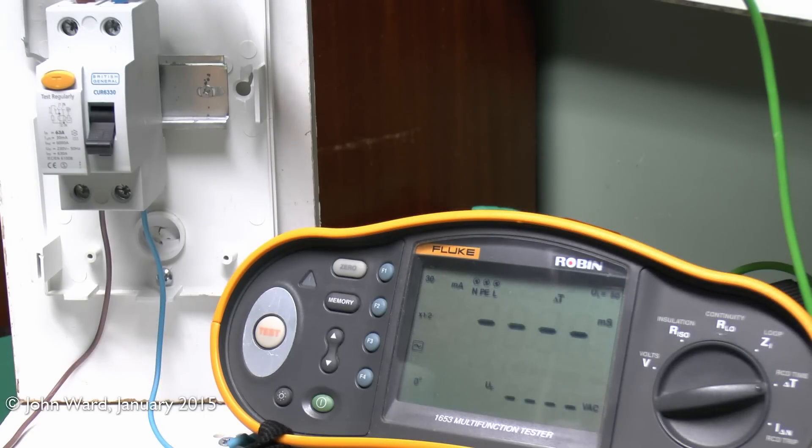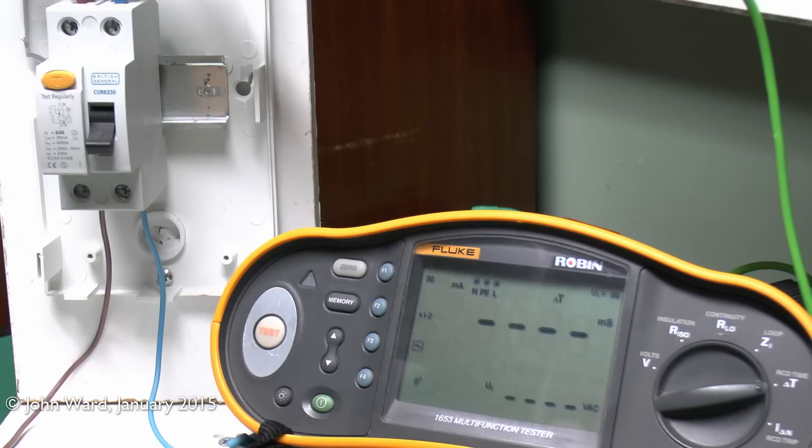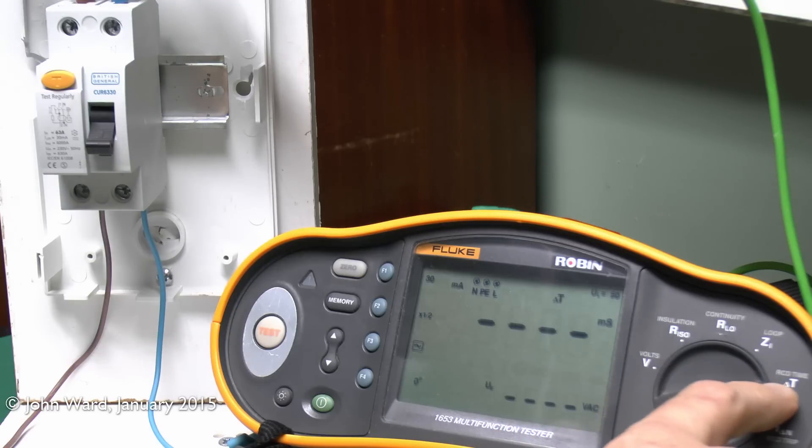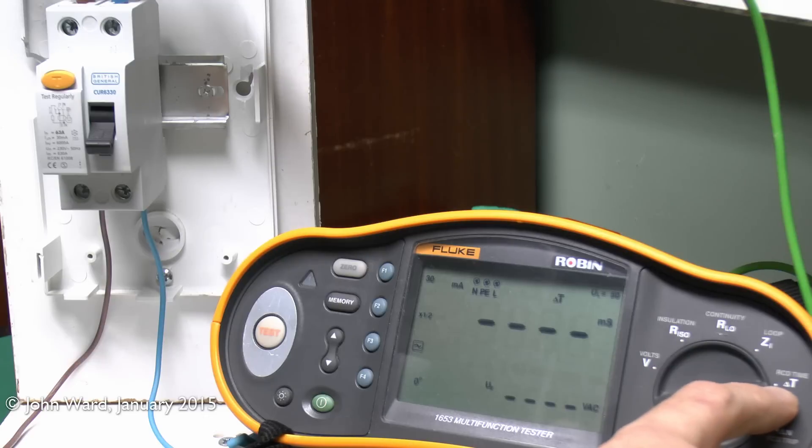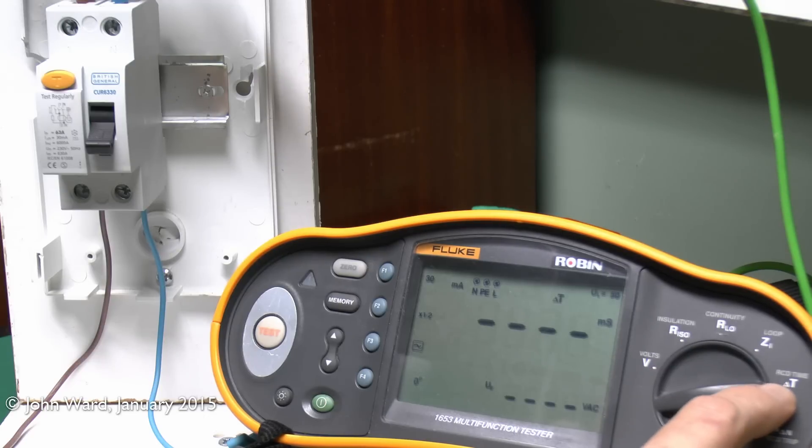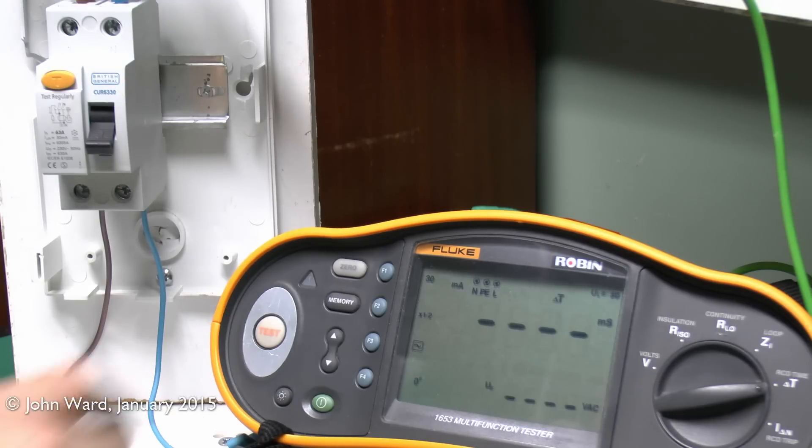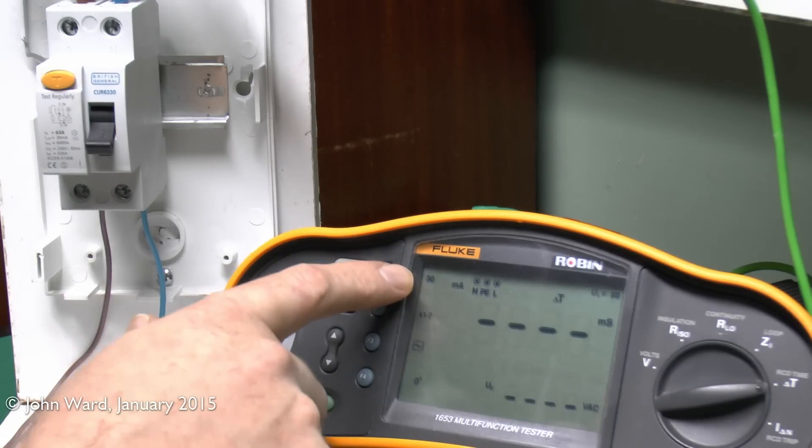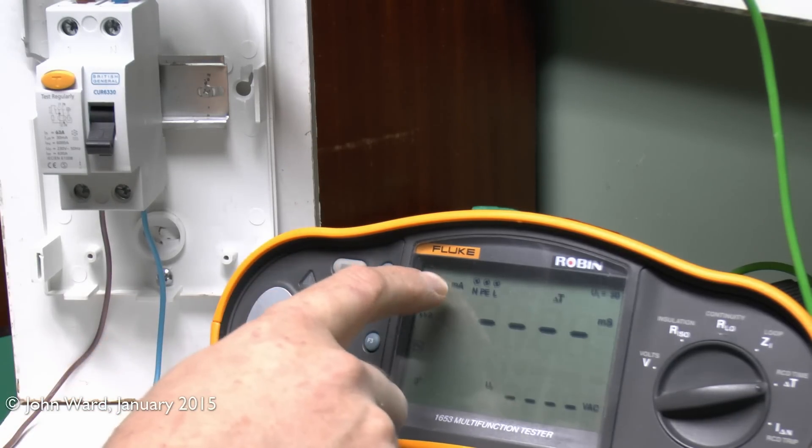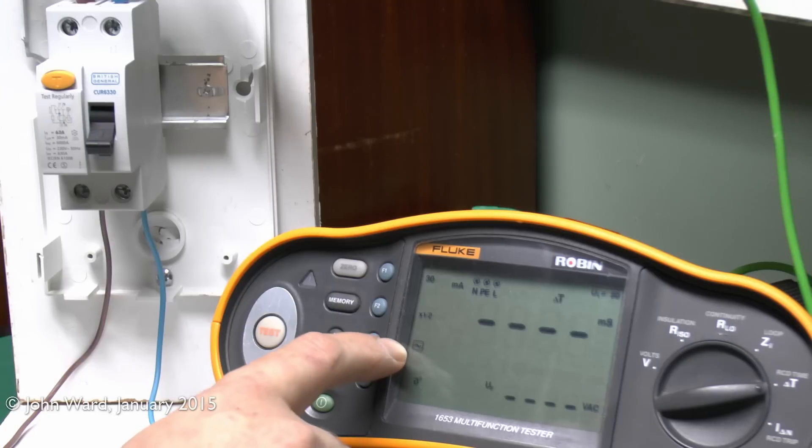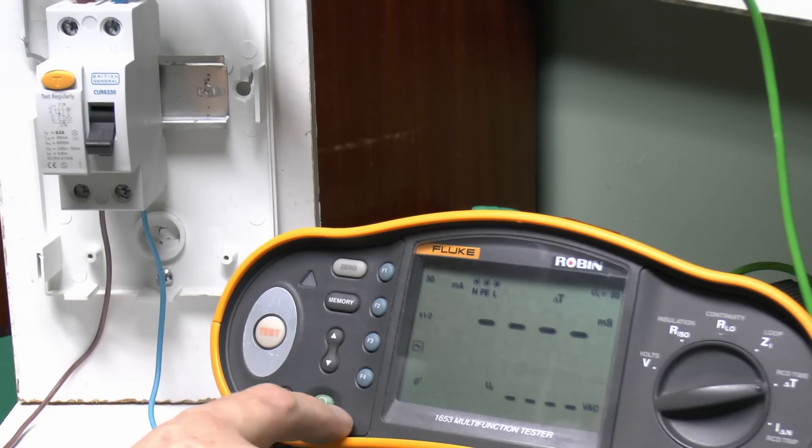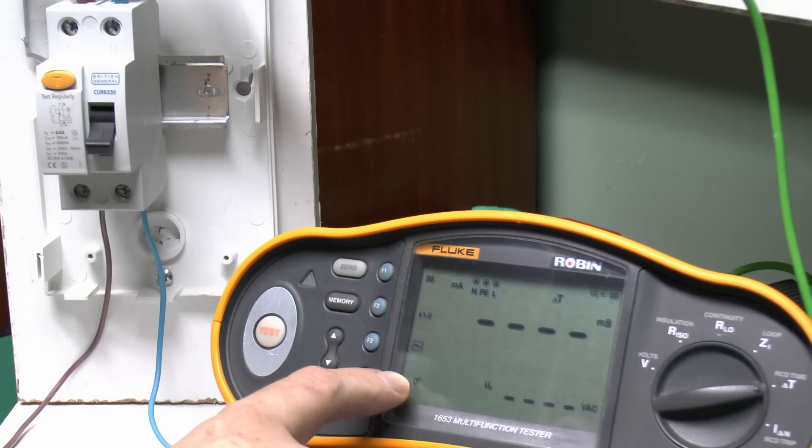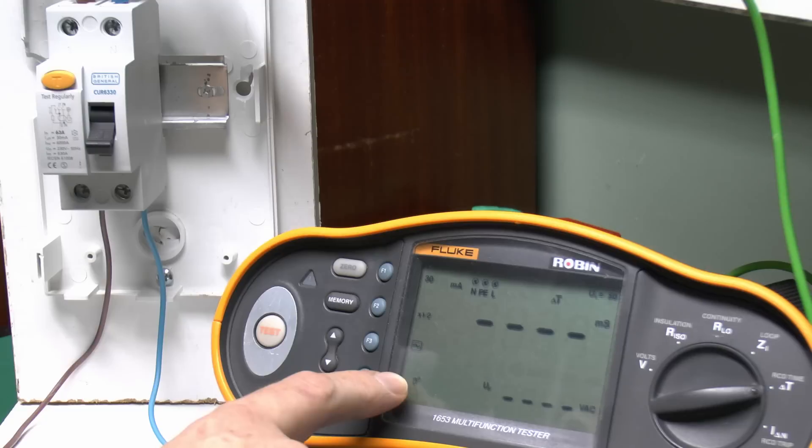Now the second type of test, and by far the most common one that's done, is the tripping time, or in other words, how long it takes to actually trip the device at various test currents. So again, we've just selected the delta T setting here, or RCD time. And the other settings are pretty much the same as before. We've got the actual current rating of the device, so 30 milliamps. The type of device, again, just the ordinary AC variety. And we've still got those 0 and 180 degree options as well.